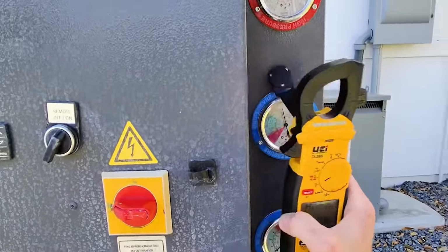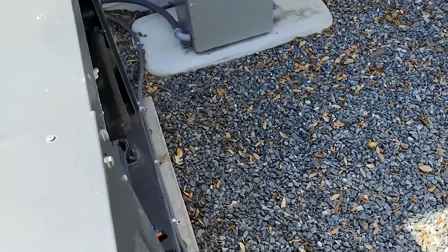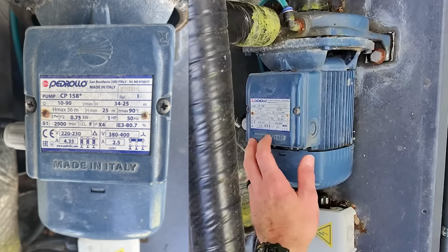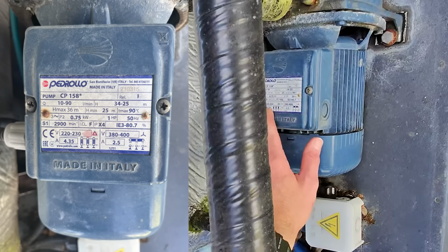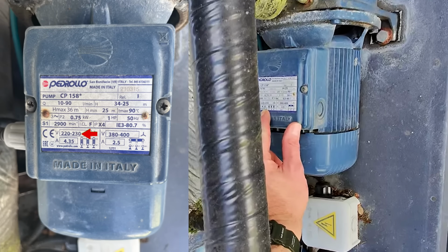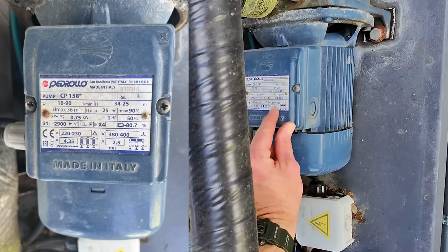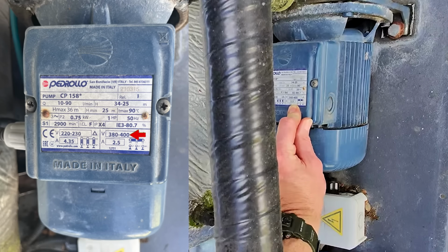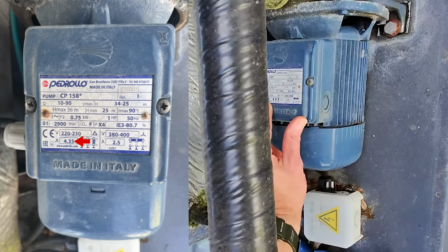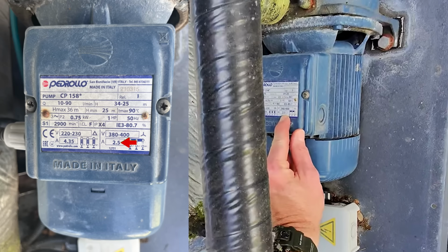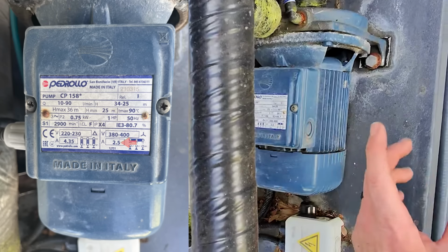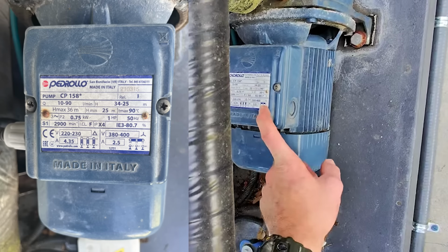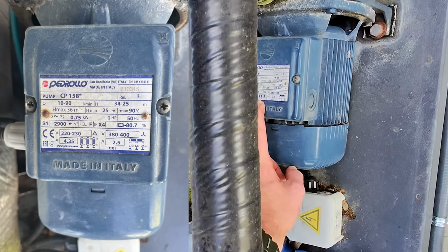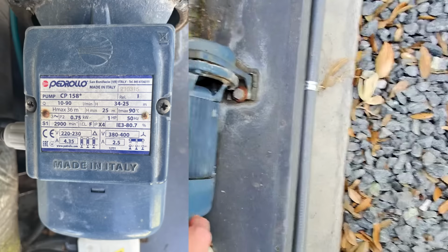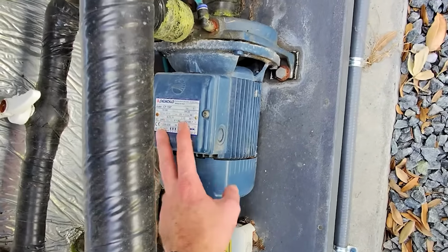We can go over to our motor, which would be the next step here, and look at our nameplate. And if we do, you'll see here we've got two different ratings. We've got 220, 230 volts at 50 hertz, and we've also got 380, 400 volts. And so both of these, this looks like a 4.35 amp rating. This is a 2.5 amp rating. I would almost love to see what's inside here to see, is it wired for 220, 230, or is it wired for 400? So it has been running, but that doesn't mean that it was wired for the right voltage.